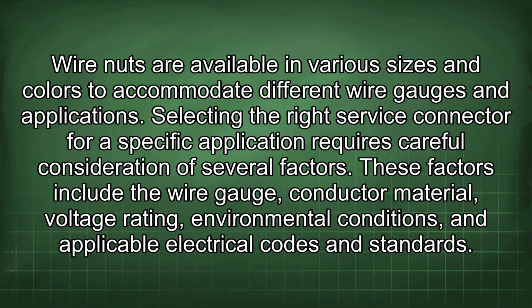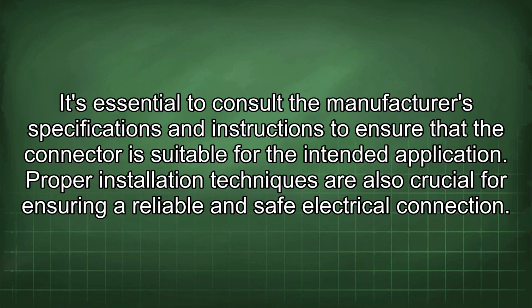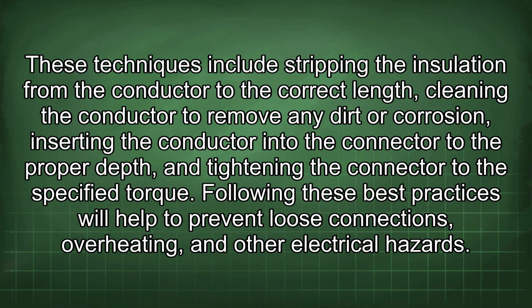These factors include the wire gauge, conductor material, voltage rating, environmental conditions, and applicable electrical codes and standards. It's essential to consult the manufacturer's specifications and instructions to ensure that the connector is suitable for the intended application. Proper installation techniques are also crucial for ensuring a reliable and safe electrical connection. These techniques include stripping the insulation from the conductor to the correct length, cleaning the conductor to remove any dirt or corrosion, inserting the conductor into the connector to the proper depth, and tightening the connector to the specified torque. Following these best practices will help to prevent loose connections, overheating, and other electrical hazards.